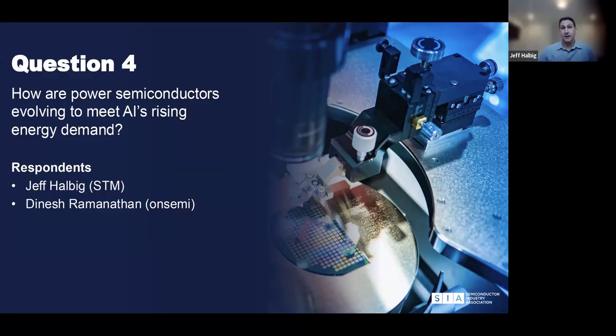And evolving silicon carbide to very high voltages, the 2.3 kilovolt and 3.3 kilovolt devices, is enabling the solid state transformers already discussed. These systems take the big, bulky linear transformers you're used to seeing on power poles, along with multiple steps of power conversion, and condense them into one. So now you can go from medium voltage on the grid right to 800 volts, straight into the data center rack, instead of having 2-3 different conversion steps. Also, the solid state transformer enabled by very high voltage silicon carbide gives you intelligence—you can do load management, safety precautions, all sorts of intelligent power design with power semiconductors rather than passive components.